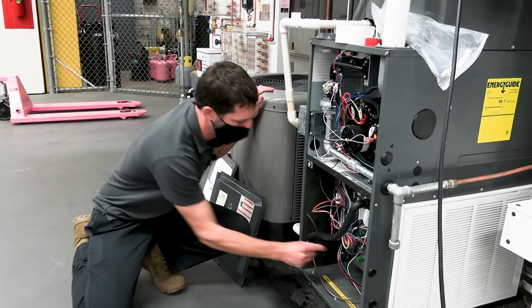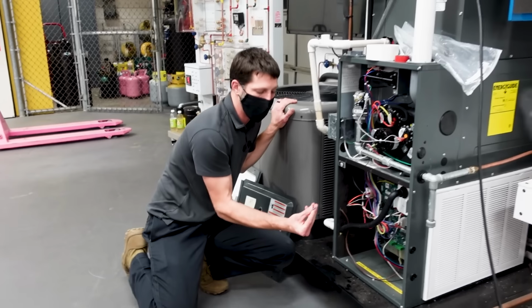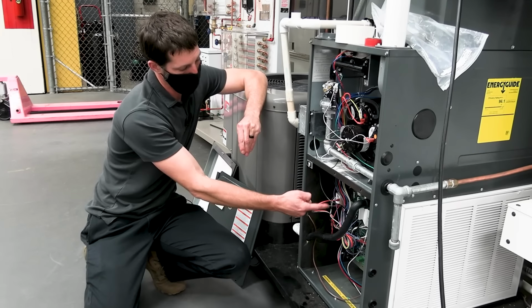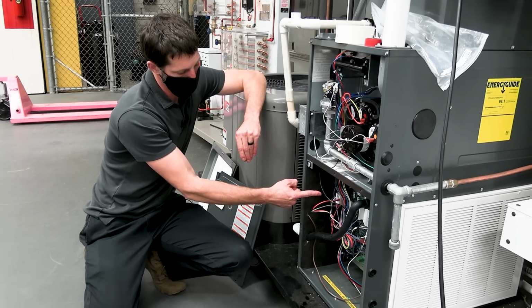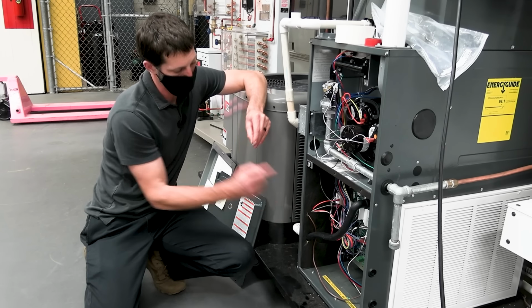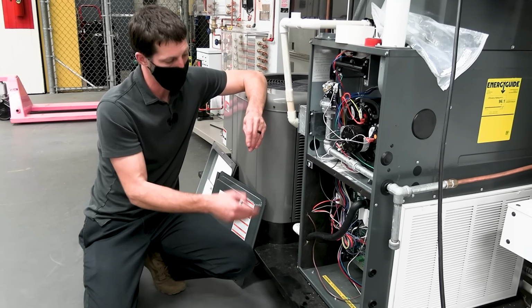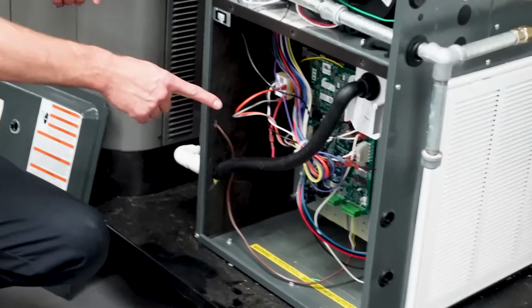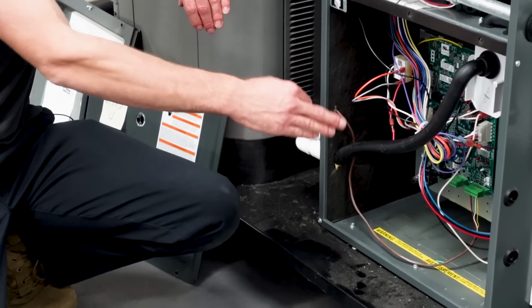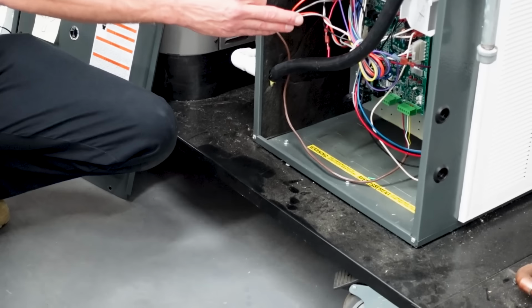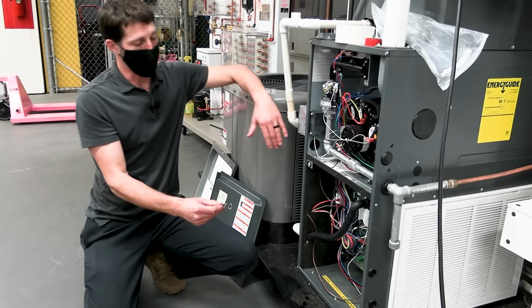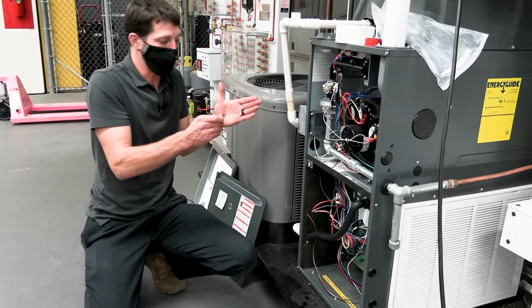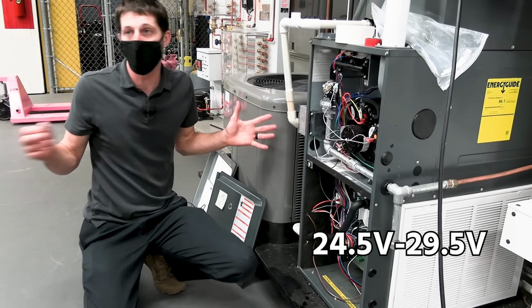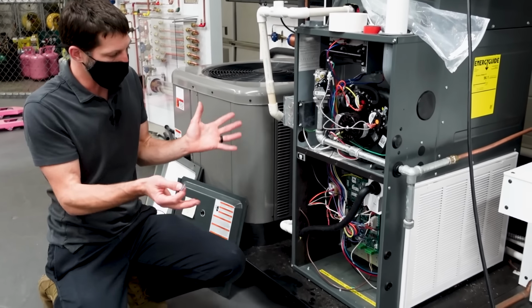In this case, once again, the power is off. You have a 3 amp fuse right here. The power is going to go from the hot of the transformer. It's going to go into the control board. It's going to go through the fuse, and then from there, it's going to power your status light, and then also going to go to the R terminal. You can measure it with a multimeter between R and C just for main power. And 24 volt will measure anywhere from, say, 24.5 volts to 29.5 volts. That's usually around what it is.